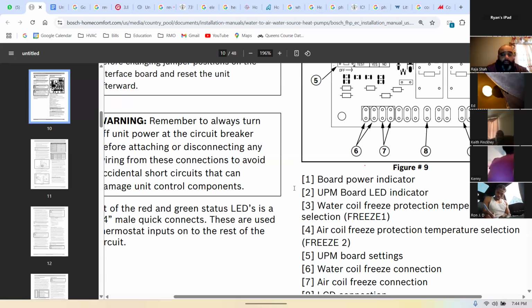So, for example, my inducer draft motor is not blowing, okay, and I jump it out. Or I have a hole in my heat exchanger, so I'm getting issues with the pressure switch. I jump out the pressure switch and I've got a flame flowing back through my heat exchanger, shooting the flame back at me. Well, I've seen all kinds, so be careful when you're playing with the safety.